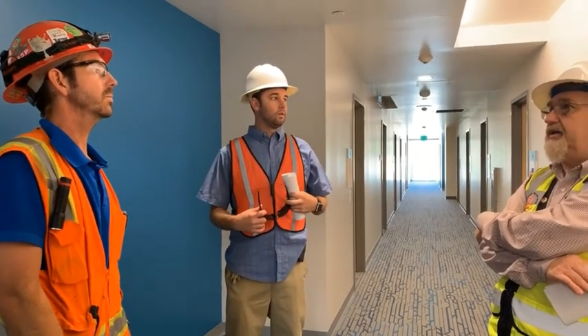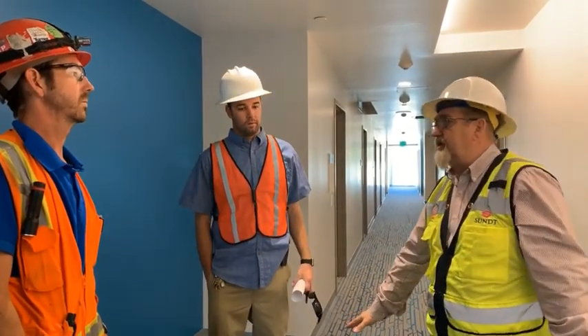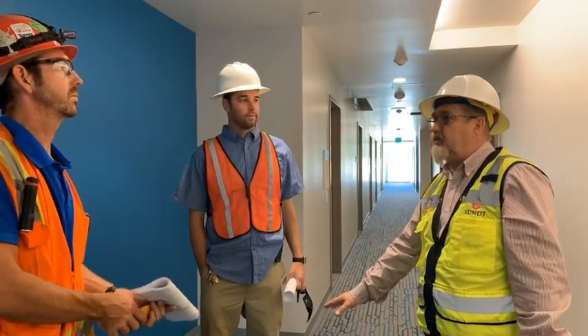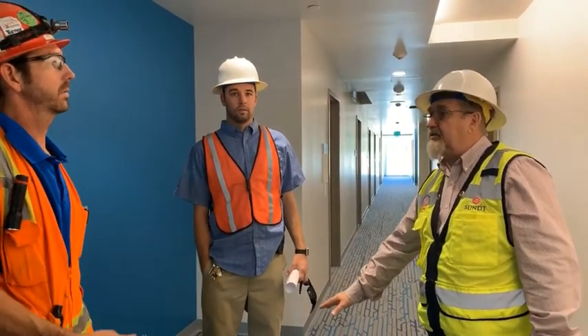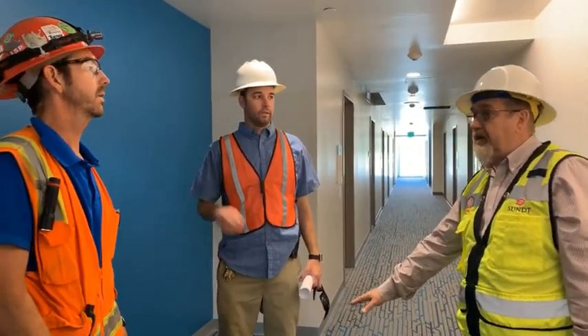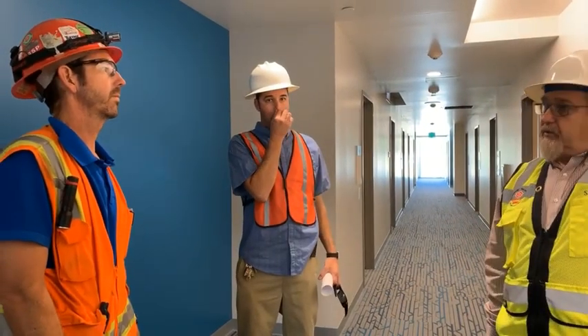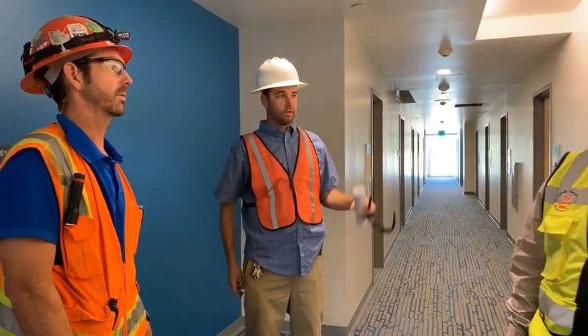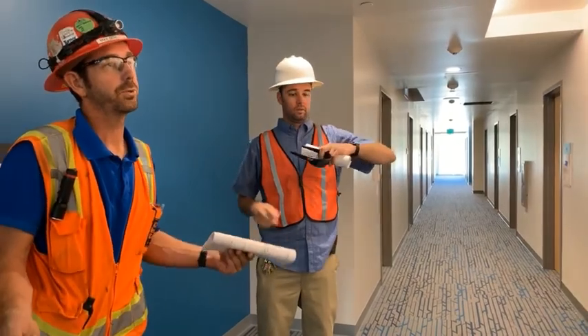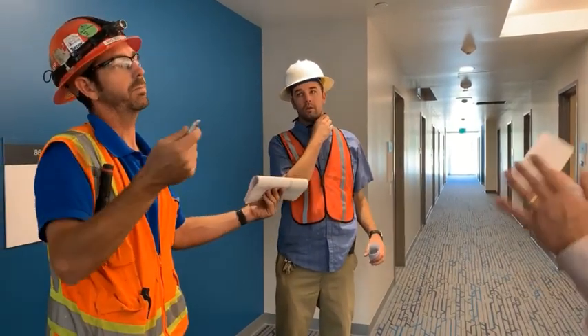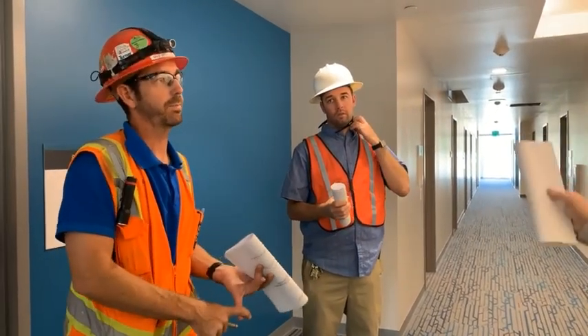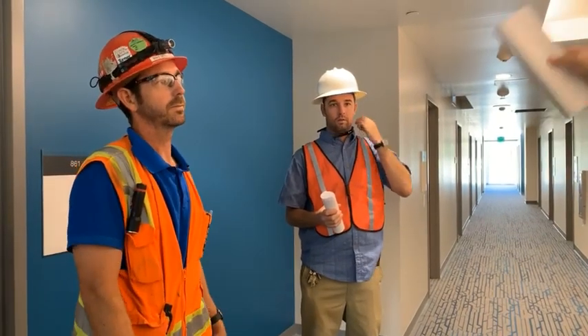Just one quick question. Down in the mechanical room, on the floor, there was the pressure regulator for the hot water. The small one? That was the red expansion tank? The red one, yes. And then the big tall one, what was that? Heating hot water. Got it. Since your chilled water is tied into the campus loop, you don't need all that. Right. Same with the air separator and all that stuff, it's a gravity system.